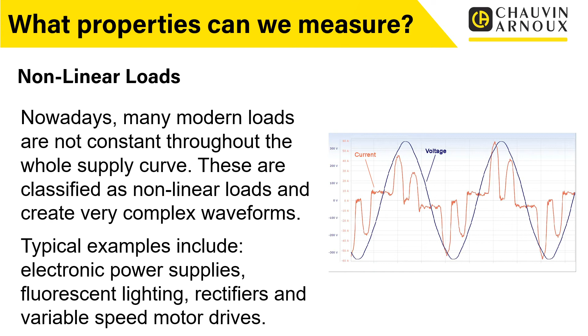These are classified as nonlinear loads and create very complex waveforms, as you can see on the right-hand side there - that's a typical waveform for an electronic power supply. It's drawing current at certain parts throughout the waveform, not throughout the whole curve. Typical examples include electronic power supplies, fluorescent lighting, rectifiers, and variable speed motor drives. We're getting more and more of these in electrical installations nowadays.